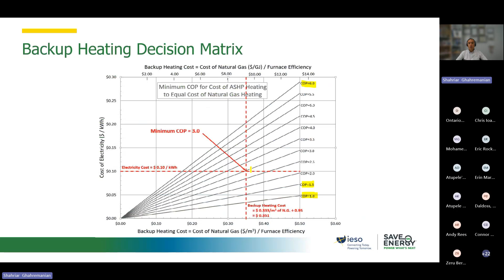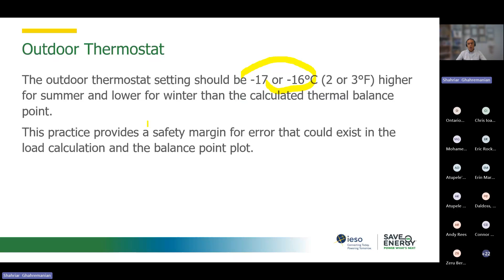I want to mention that the outdoor thermostat also needs to be set. For example, for these temperatures that we have for summer and for winter, this also has an impact on the COP and operation of the heat pump. And usually the trades or contractors consider a safety margin of error when they set up, based on the balance point and the calculation of the output of the heating that we have from the heat pump. I will go very quickly over the terminologies that you might hear about heat pumps.